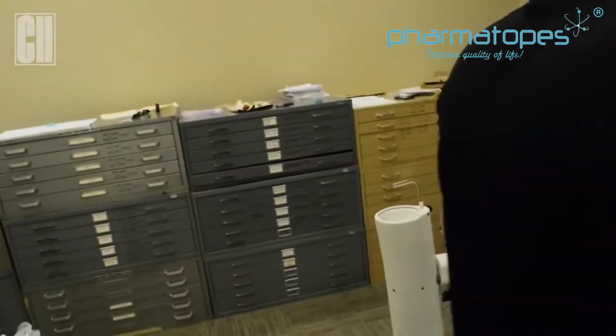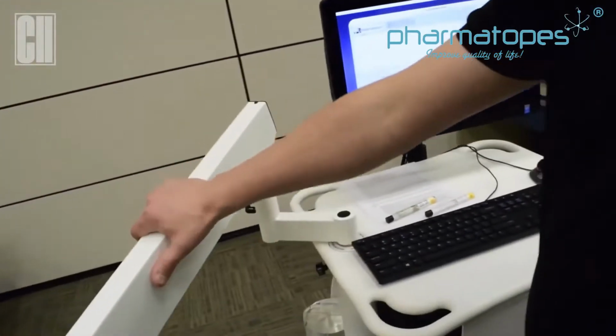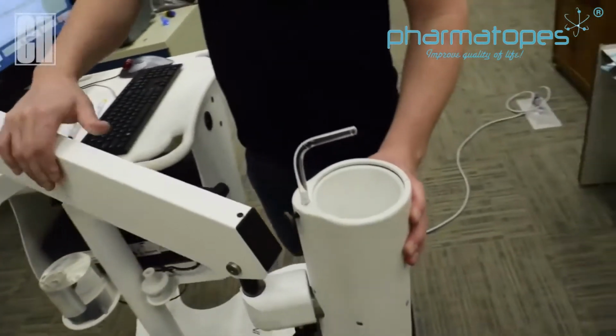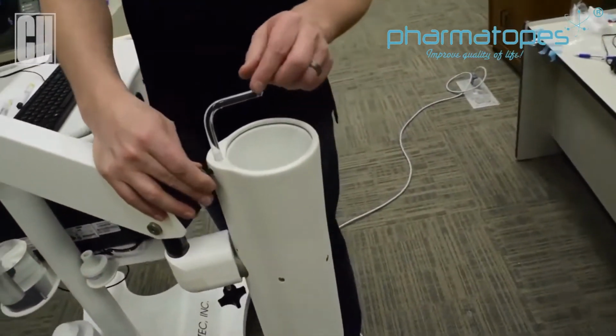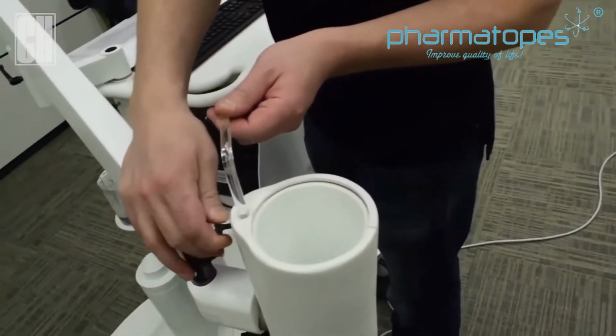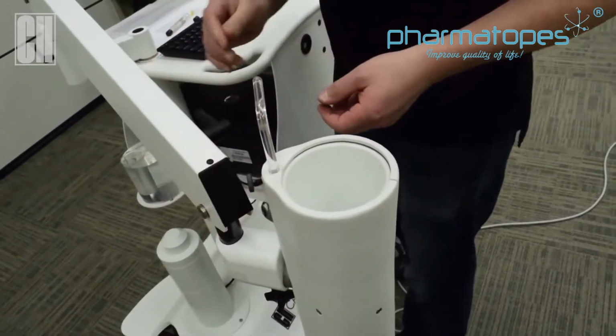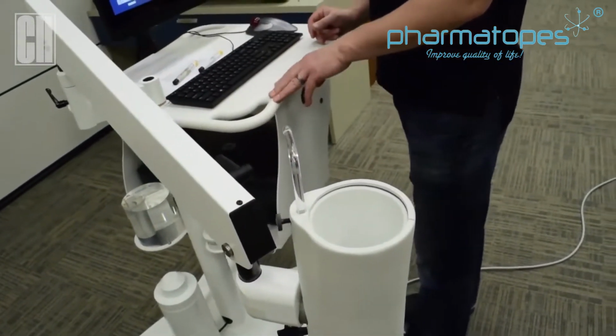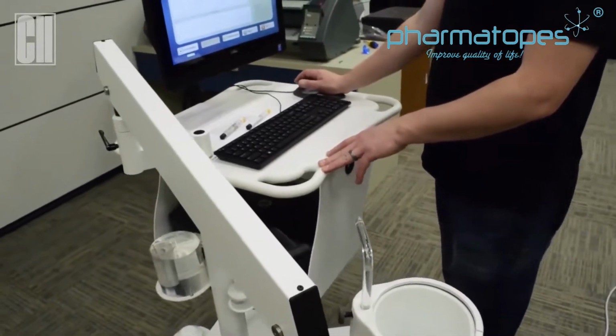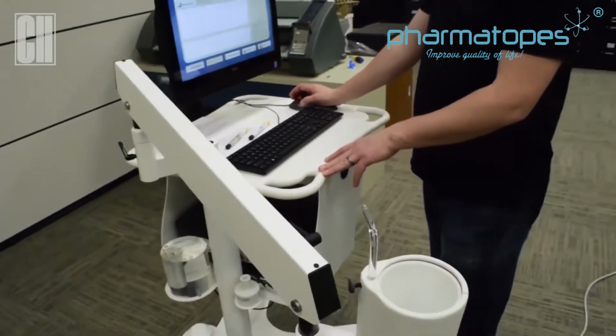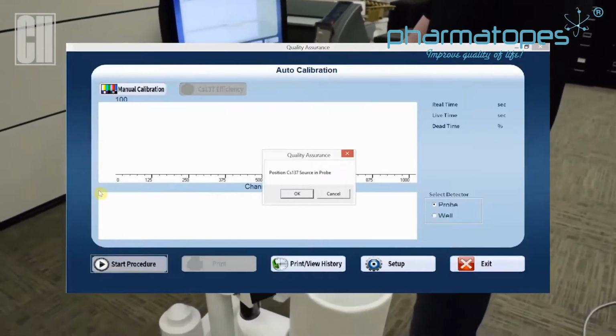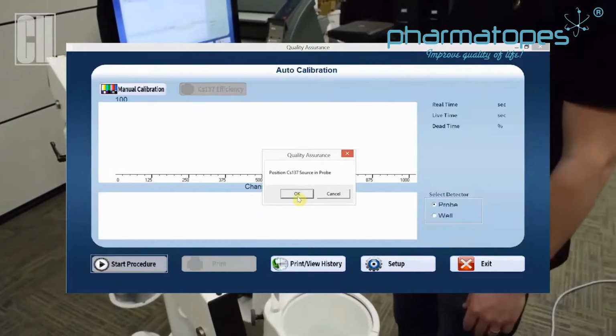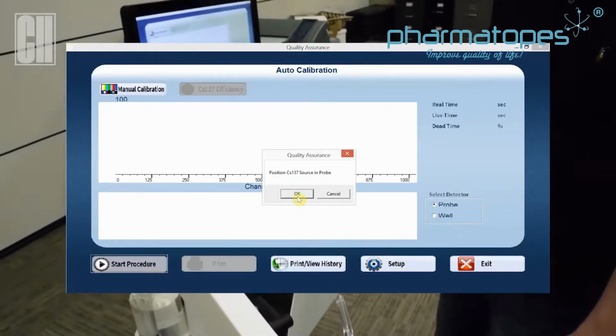So what we're going to do is start with the probe. So we're going to get the probe into place and then loosen the screw and turn the pointer rod out of the way to begin our calibration. So what we'll do now is click on start procedure, and the software will prompt you through each step. It's telling us to position cesium in the probe.